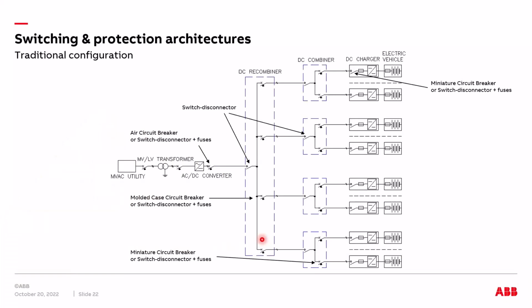So, talking about the possible switching and protection architecture, we can have 3 main philosophies. First of all, we have the traditional configuration, as you can see, made of traditional switching and protective devices: a circuit breaker, molded case circuit breaker, or switch disconnector plus fuses, and miniature circuit breakers installed inside our DC charger according to the rated power of the chargers.